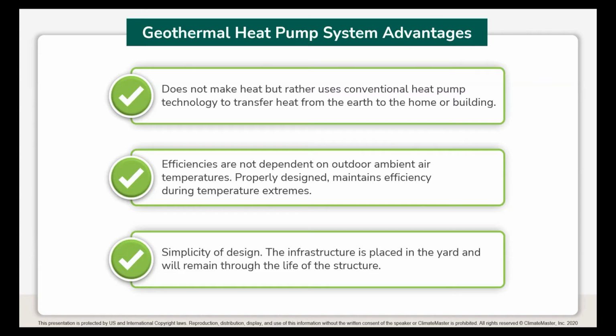Efficiencies, again, are not dependent on outdoor ambient temperatures. Properly designed, and we encourage you not to stray from the design requirements of a structure with a ground source heat pump, because if we start straying from proper design, in the end, we'll have an unhappy homeowner. Properly designed, it maintains the efficiency during extremes.